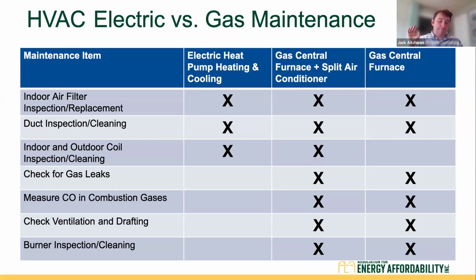Now, these maintenance items are really preventative for dangerous combustion gas issues. However, based on the data that I shared and the testing that we've seen, people often don't do these maintenance items, and they should be doing these maintenance items. And so you can imagine that the perception is that gas appliances require less maintenance, but in reality, you should be doing this. And if you're not testing for these items, one of these issues could be true in your existing building. So just calling that out.